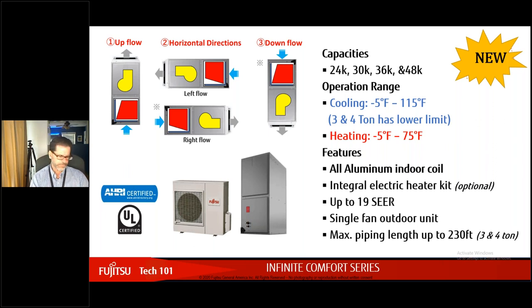Now, that might sound all impressive. And you look down the street next time you're out and go, well, how far is 230 feet? It doesn't mean we should always go that far. With refrigerant, you have derating. The further you travel, you'll have derating. So you can't promise you're going to deliver the BTUs that we're stating. So shorter is always better above minimum.